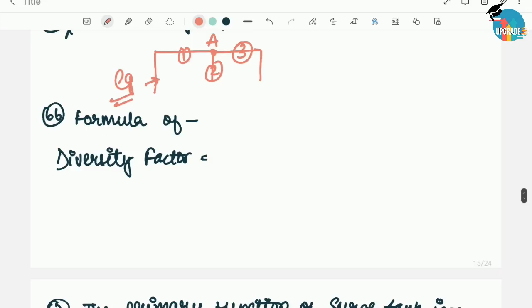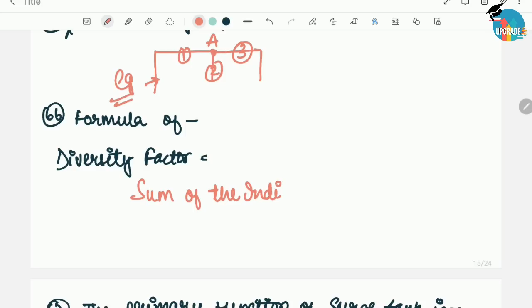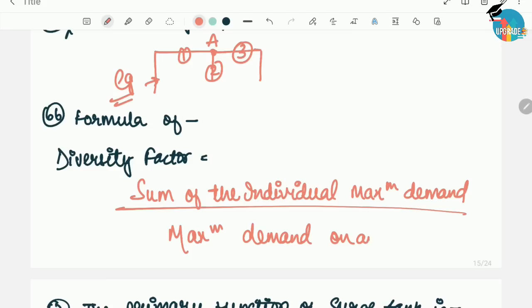The next question asked for the formula for the diversity factor. It is the sum of the individual maximum demands divided by the maximum demand on an alternator. This is the correct formula, and the value of the diversity factor is always greater than 1.